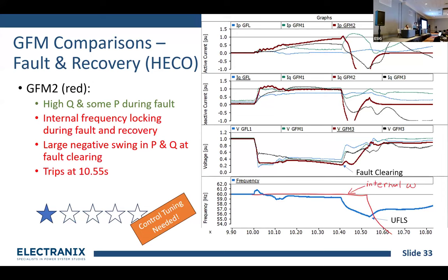The next one is a grid forming response and it's quite interesting. We know a little bit about how the guts are working — it's locking its internal frequency during the event. The grid frequency is 59.5 Hz but the internal frequency is about 60 Hz, so we get a divergence in the angle between the internal angle and the system angle at fault clearing. Due to that, in a situation where the system is very megawatt and megavar deficient, this grid forming inverter actually absorbs megawatts and megavars from the system — doing the opposite of what we want — and ends up tripping. This is kind of the equivalent of pole slipping for grid forming controls. Control tuning is needed; they need a better way to synchronize the internal angle to the grid angle while current-limited.